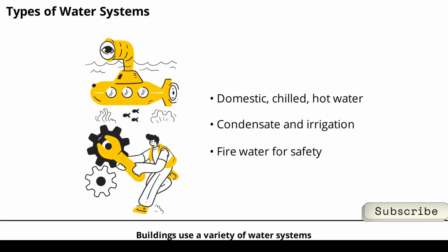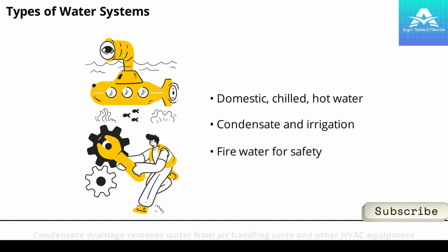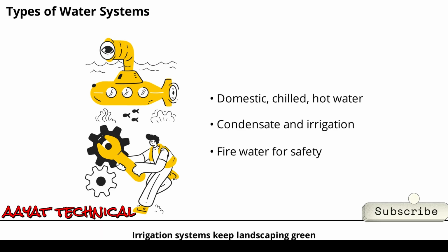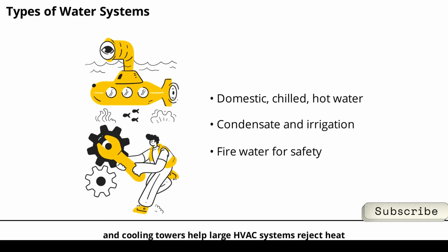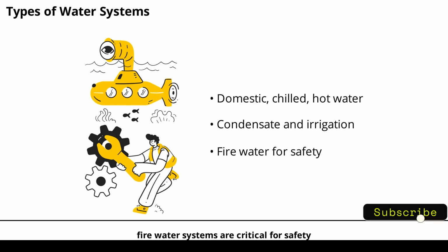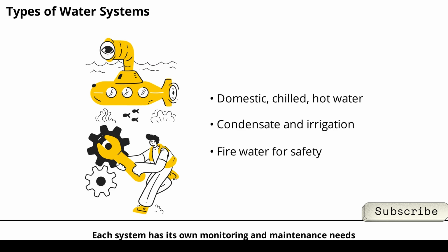Buildings use a variety of water systems, each serving a unique purpose. Domestic water supply delivers drinking water and supports kitchens and restrooms. Chilled water loops cool the building through HVAC systems, while hot water systems provide heating or hot tap water. Condensate drainage removes water from air handling units and other HVAC equipment. Irrigation systems keep landscaping green, and cooling towers help large HVAC systems reject heat. Finally, fire water systems are critical for safety, powering sprinklers and hydrants. Each system has its own monitoring and maintenance needs, making BMS integration vital.